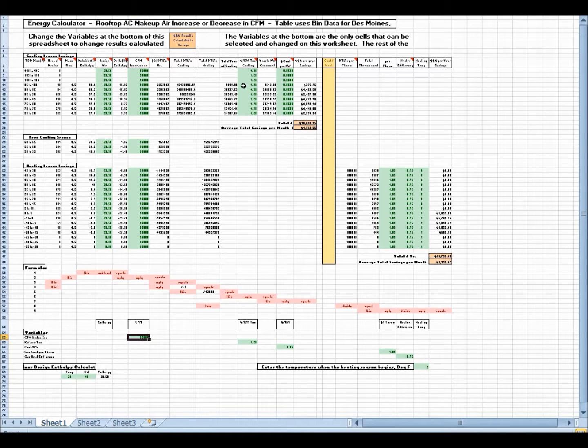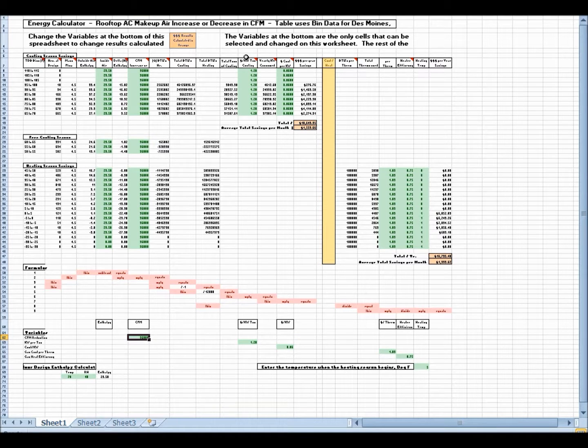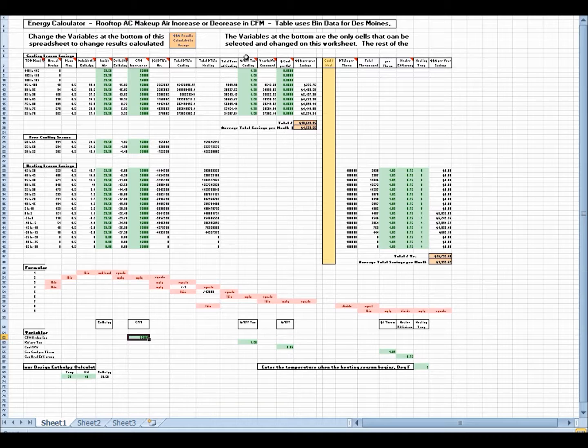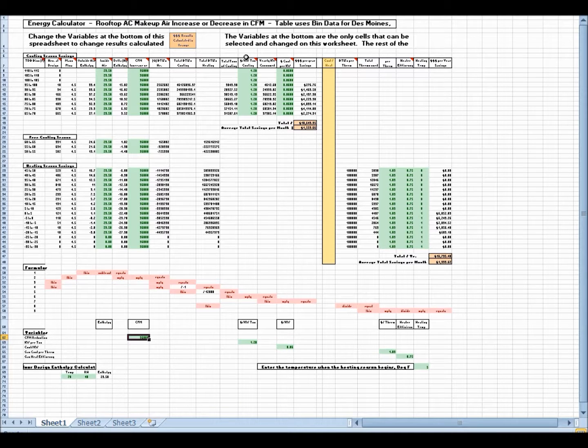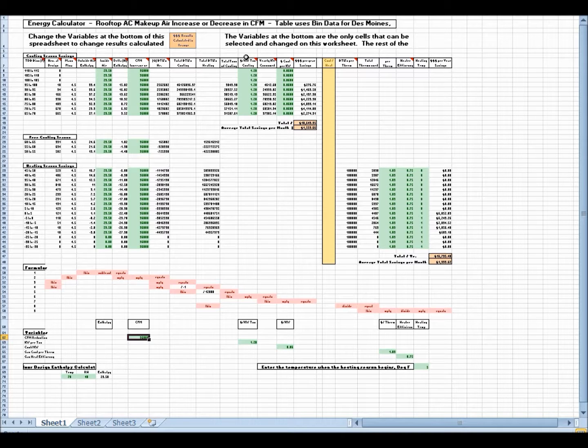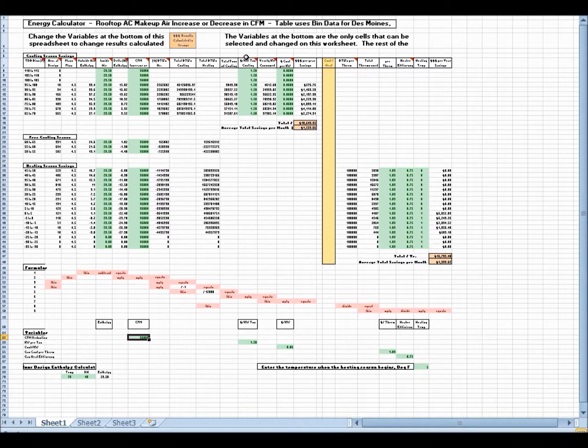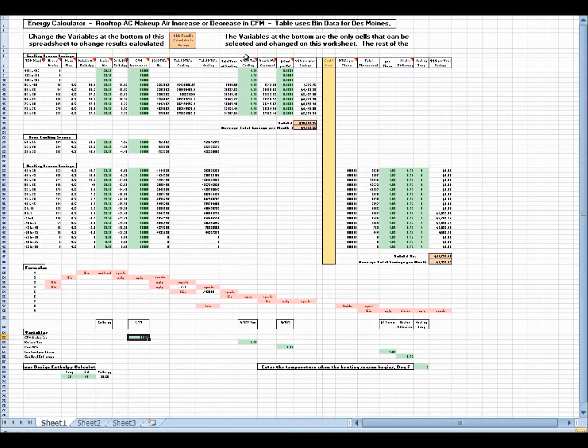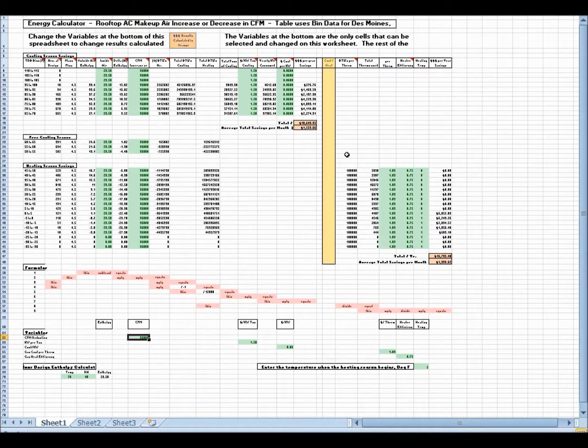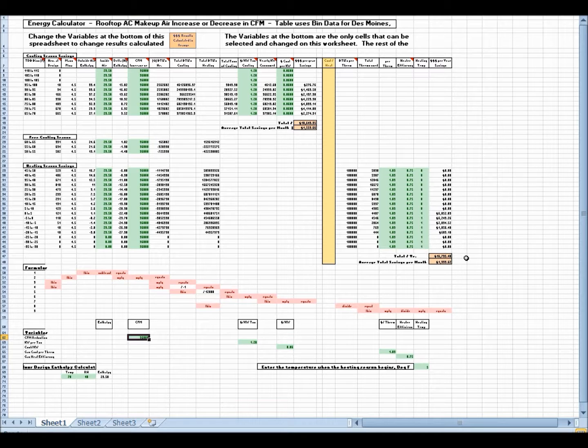And the other value right here is KW per ton. It costs you to cool your air conditioner. That relates back to an EER energy efficiency ratio or an SEER energy efficiency ratio. And how accurate is that? They state that, but as air conditioners get old, condensers get dirty, equipment gets old, that can change. So that's another value that makes this total calculation an approximation.